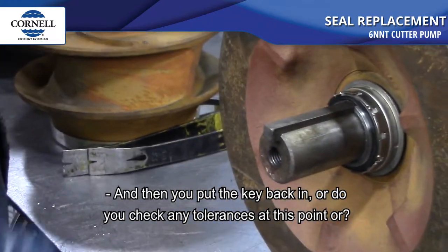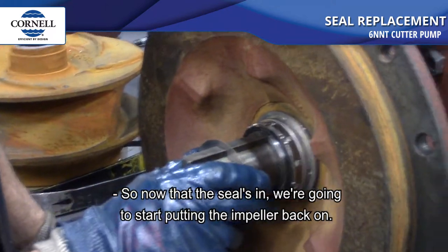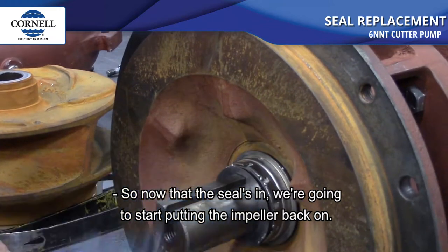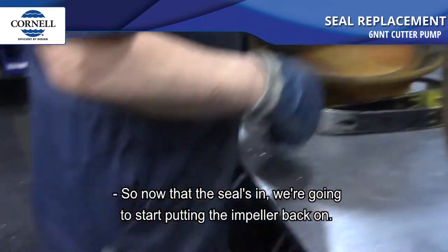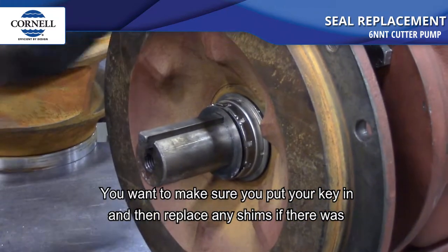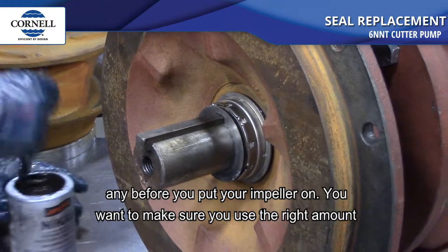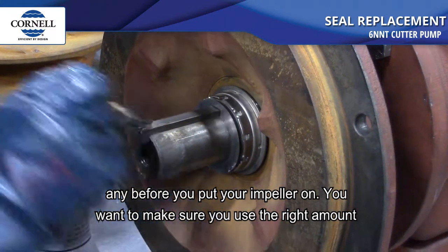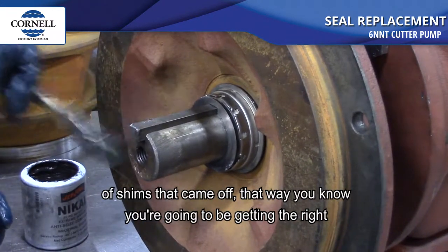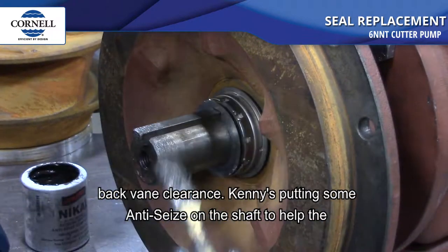Now that the seal's in, we're going to start putting the impeller back on. Make sure you put your key in and replace any shims that were there before you put your impeller on. Use the right amount of shims that came off — that way you know you'll get the right back vane clearance.